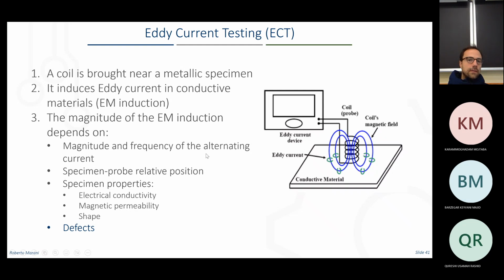It depends on the current that you are using as an input, for sure, so from your sources, then from the relative position of your coil and the conductive material that you are testing, but also from the specimen properties, so conductivity, permeability, the shape of your specimen. In this case it's completely flat, but if it has a peak, for example, you can get some other distribution of the eddy currents, and finally it could depend on defects within your conductive material.